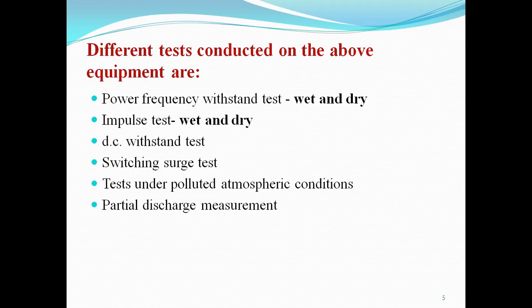Different tests conducted on the above equipment in the high voltage laboratory are: number one, power frequency withstand test, wet test and dry test. Number two, impulse test, wet and dry test. Number three, DC withstand test. Number four, switching surge test. Number five, test under polluted atmospheric condition. And number six, partial discharge measurement. That we will discuss in detail in the laboratory session.